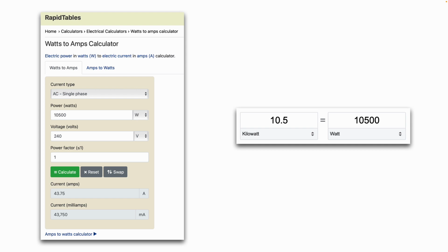In this example, we're working on AC single phase. It was rated at 10,500 watts, producing 240 volts. Leave the power factor at 1. When you hit the green calculate button, it gives us an amperage of 43.75.